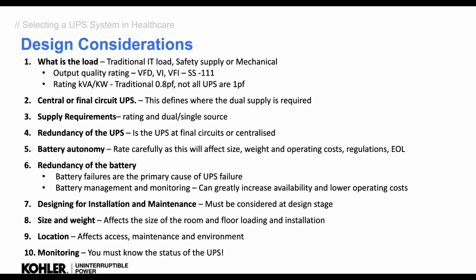We have to make sure we design for installation and maintenance. We see some awful installations, but we should be designing that in, so it's in the right environment and we can get to it for maintenance, all those kinds of things. The size and weight of the UPS is often underestimated, and so is the location where it's going to go. This cannot go in a little cupboard underneath the stairs. This has to be a proper room for the UPS to allow maintenance and make sure the environment's controlled, things like that.